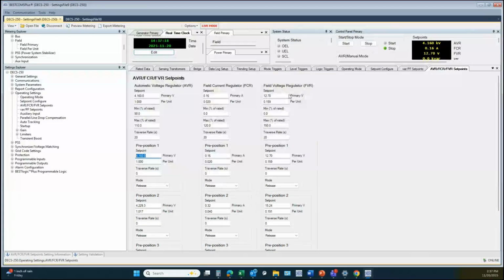FVR mode is sometimes used for certain testing, but most of the time it is not used, especially on a DECS 250 application. If you're using a DECS 250E or a DECS 450 in a static excitation system tied to the main field, and there's a field breaker in place, you might use FVR mode at some point. But again, that is a manual type of mode. It doesn't care what generator voltage is doing while you're in that mode of operation.